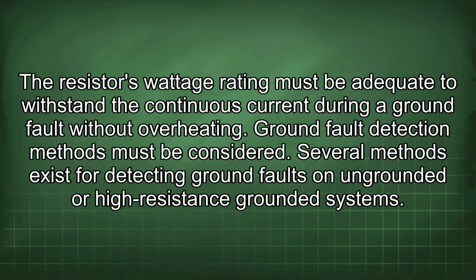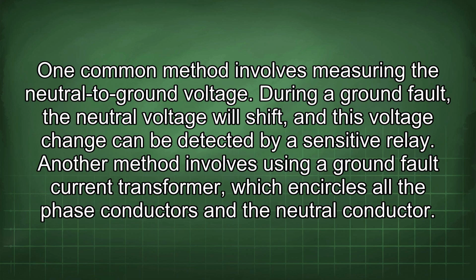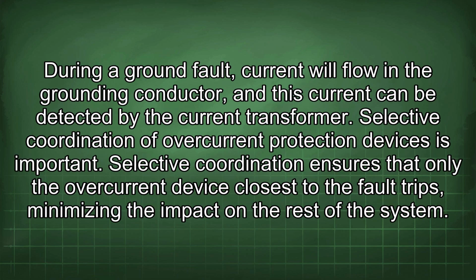Ground fault detection methods must be considered. Several methods exist for detecting ground faults on ungrounded or high resistance grounded systems. One common method involves measuring the neutral to ground voltage. During a ground fault, the neutral voltage will shift, and this voltage change can be detected by a sensitive relay. Another method involves using a ground fault current transformer, which encircles all the phase conductors and the neutral conductor. During a ground fault, current will flow in the grounding conductor, and this current can be detected by the current transformer.